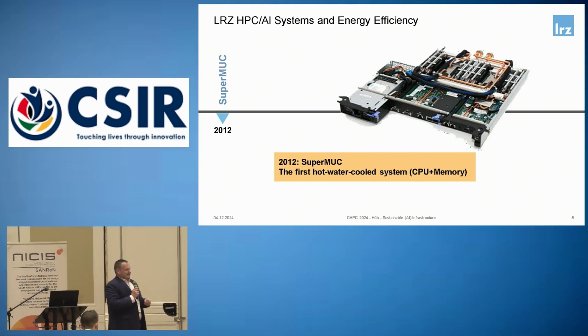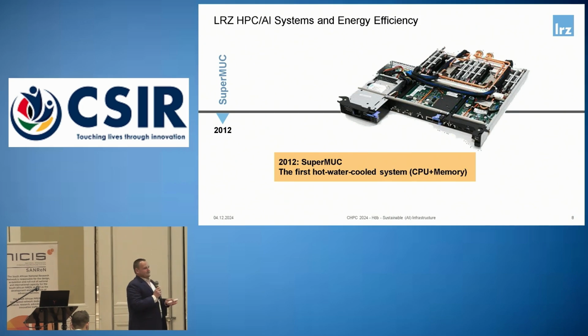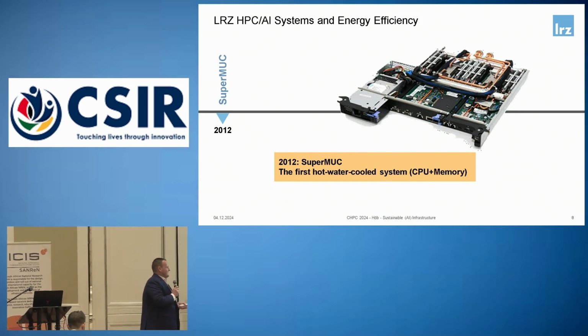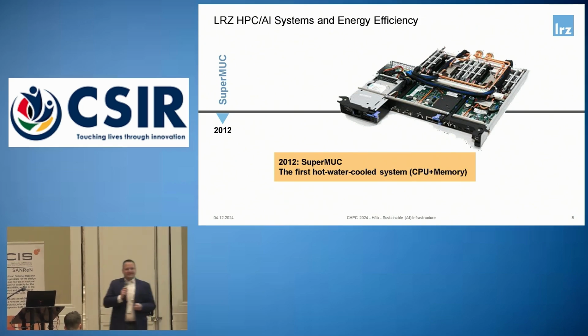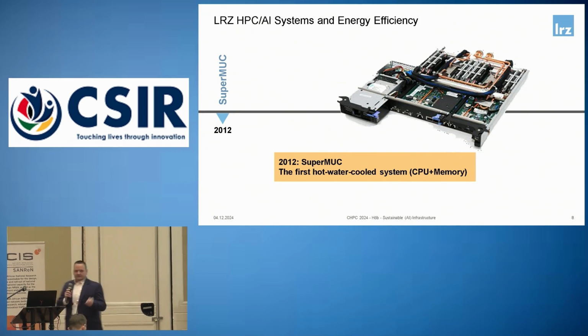We then pump the hot water onto our roof, where we have free cooling facilities, and in Munich the temperature is not likely to exceed 40 degrees for more than 2-3 days a year. That means we don't have to add any chillers for 362 days of the year, giving us a very good power usage efficiency value. I'll tell you more about that later.